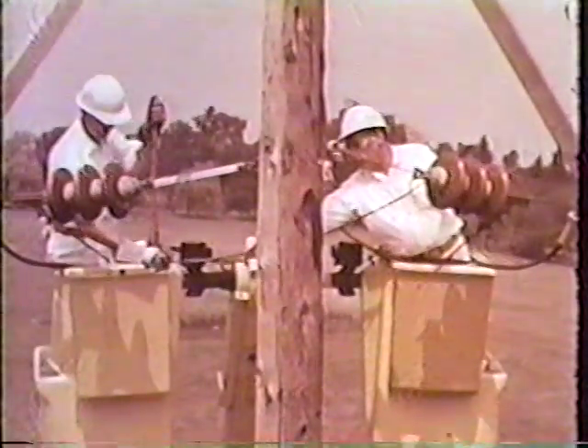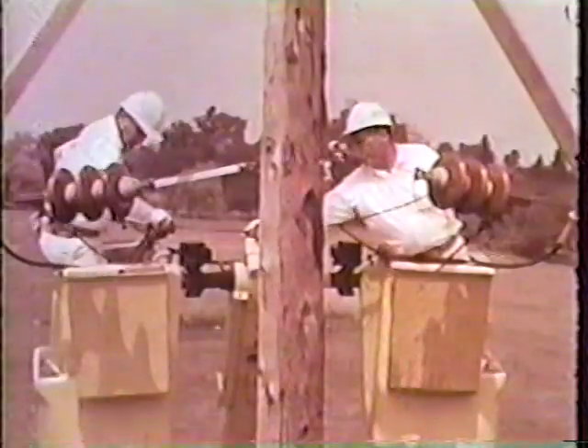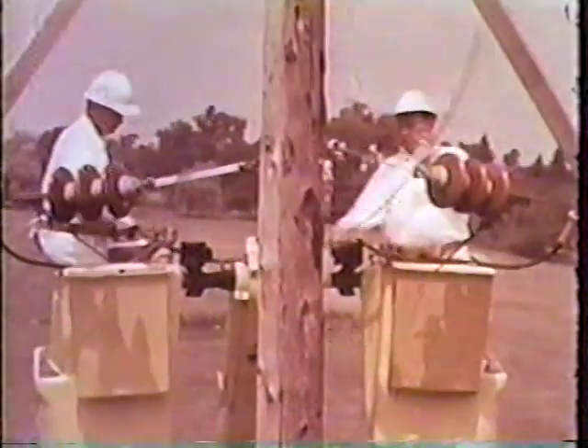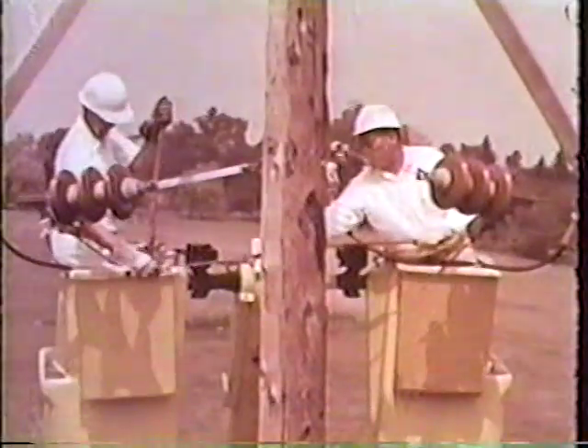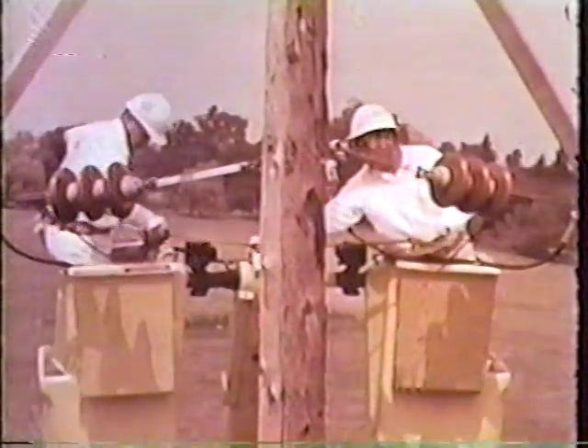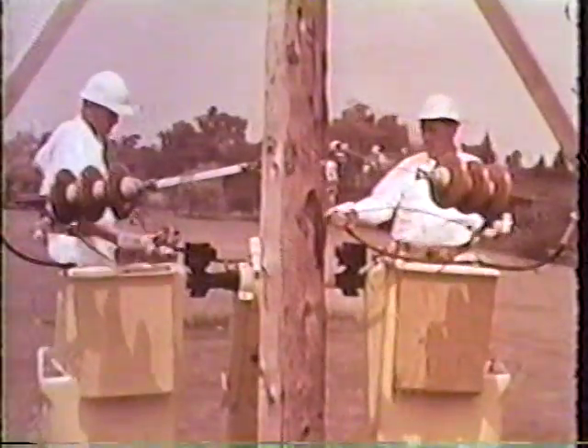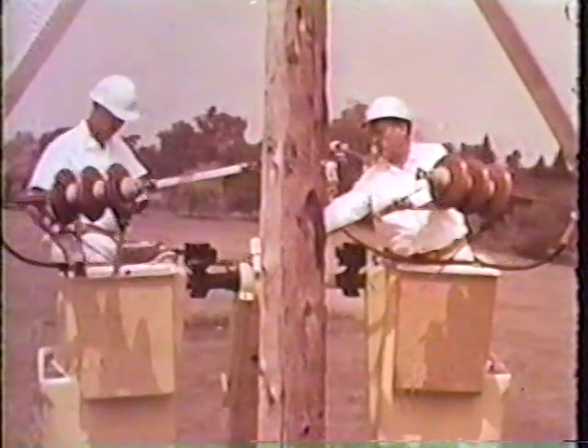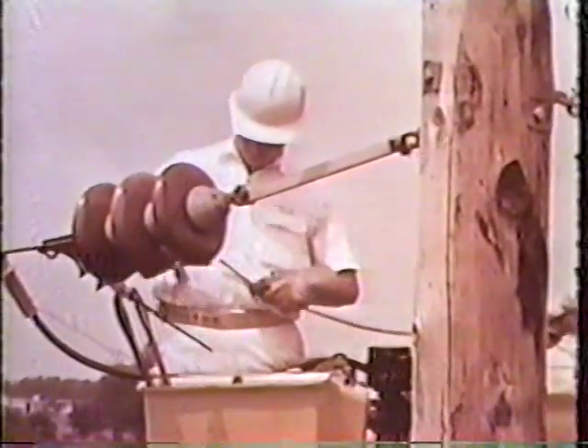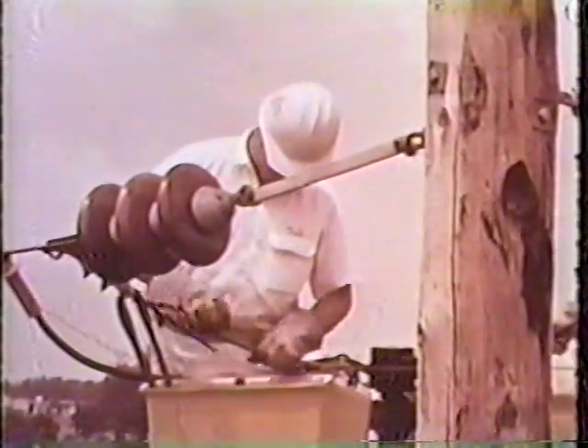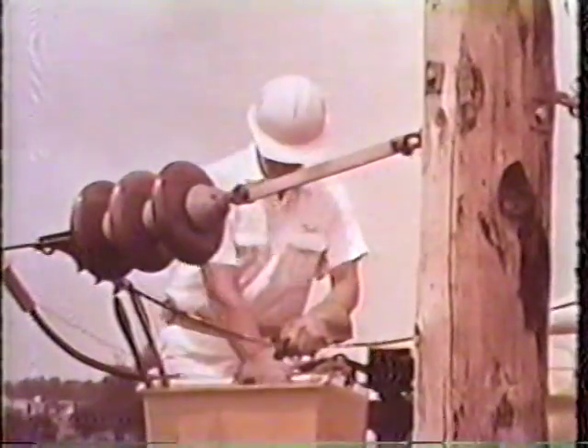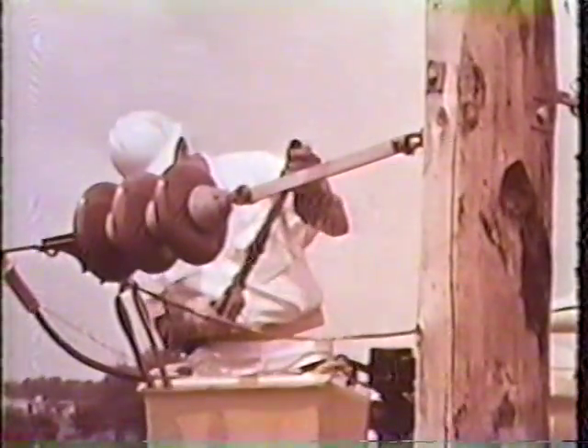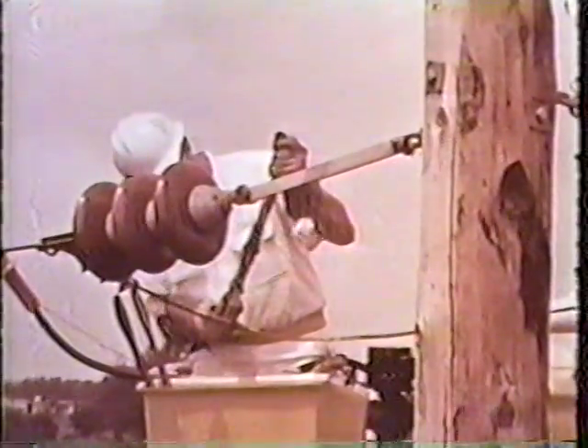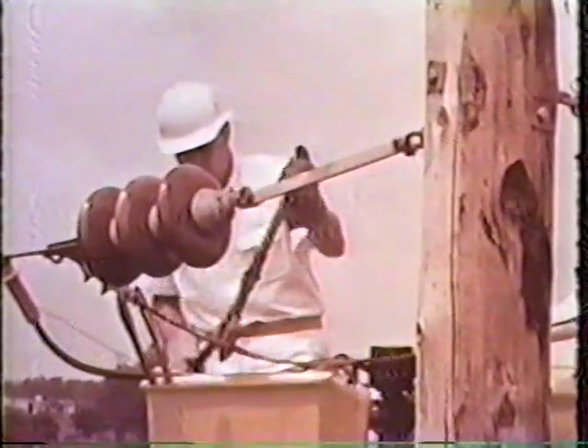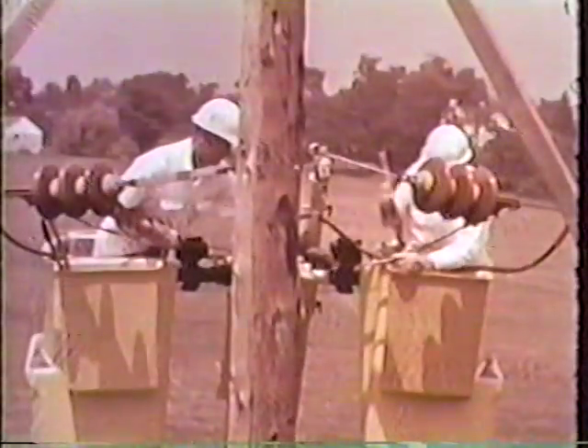After the bolted connectors are removed and the wire ends cleaned, the jumper loop is cut to size, the men helping each other from their separate buckets. The deep tool trays, made of fiberglass like the personnel buckets, are a necessity for efficient work. The compression fitting is slipped over the wire ends, and crimped, first on one side, then the other.